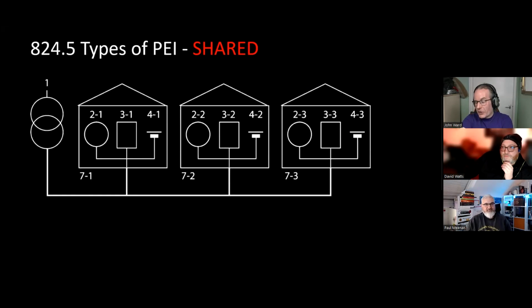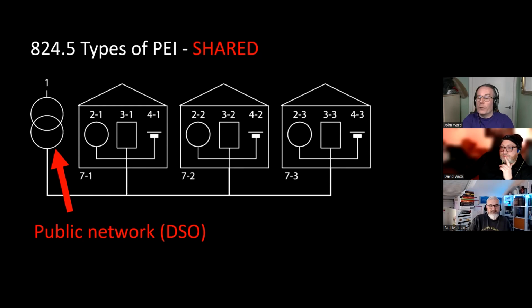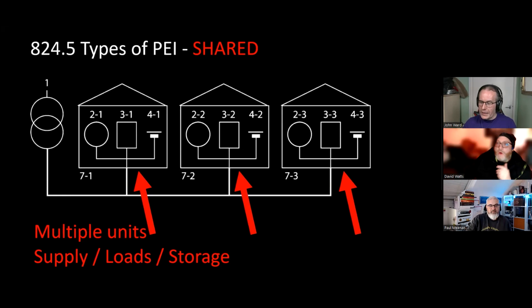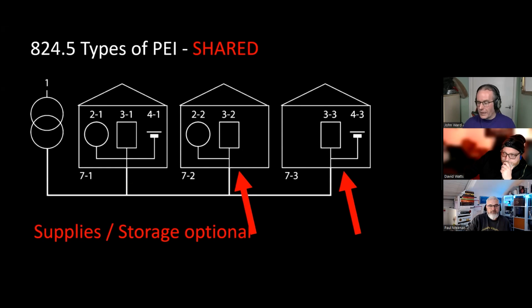And then the third type is a shared. This is similar to collective, where you've got your public network coming in, 3 properties in this illustration, but the difference here is that each individual property has its own supply, loads, and battery storage in there. So they are sharing the same network connection, and they can share things between themselves, but they can also operate individually on their own if needed, unlike the previous one where it was obviously just one set of storage for a set of people. And again, the storage is optional, so your neighbors might have batteries, you might not have. So there's all kinds of different combinations and variations on that.